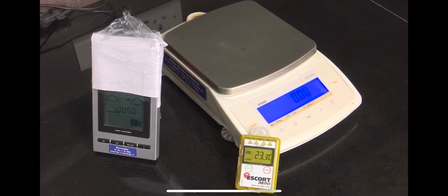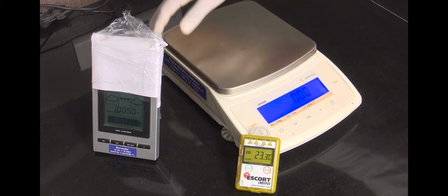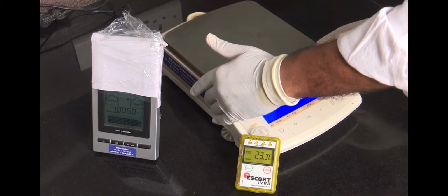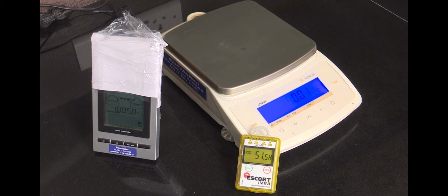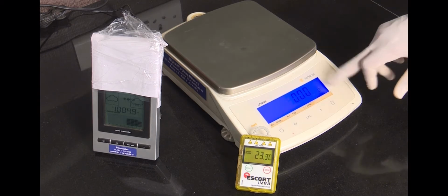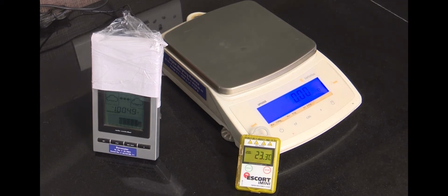I am demonstrating live display of step-by-step calibration method for weighing balance. After cleaning, visually inspect the weighing balance for any physical damage. Check the display function for blinking if any. Keep the weighing balance for at least 30 minutes for soaking at 23 plus minus 0.5 degrees centigrade so that the temperature is brought to equilibrium.